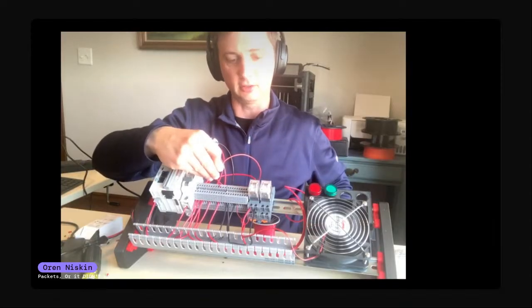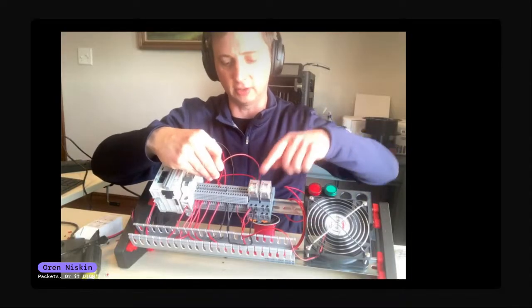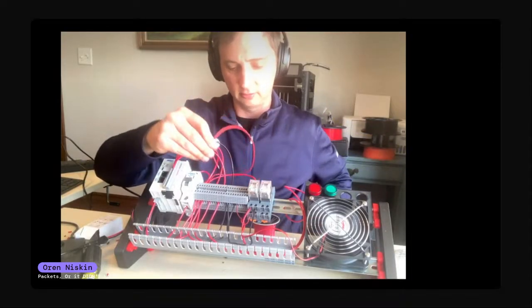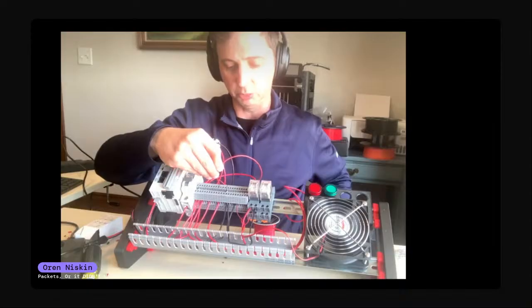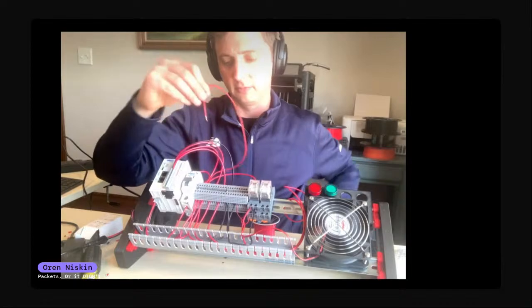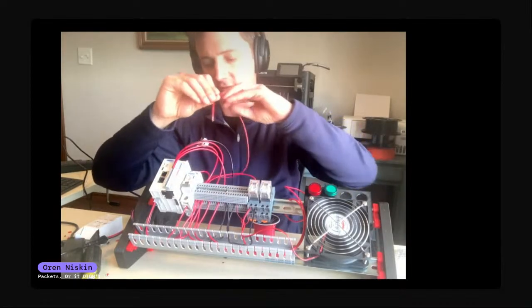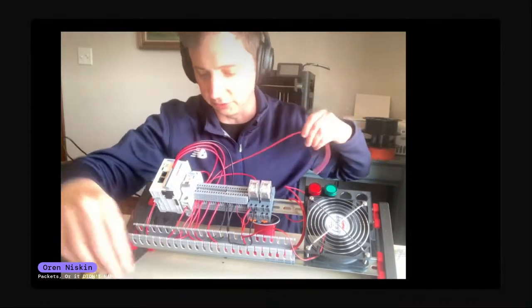And the fan starts - the relay energized and the fan started. So I am simulating the digital output from the PLC. Pretty cool. Turn it back off. Unscrew your little death wire.